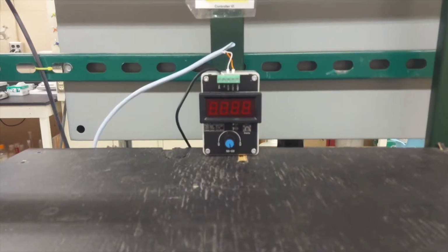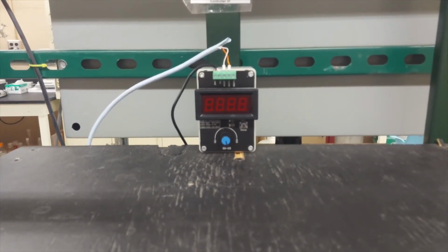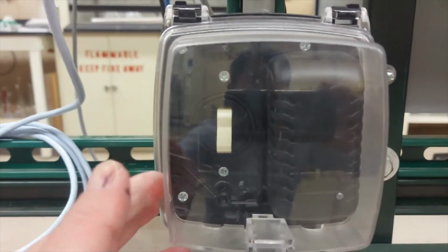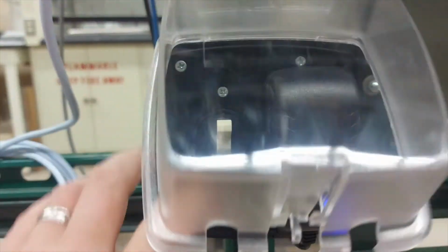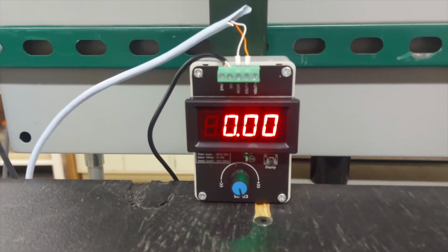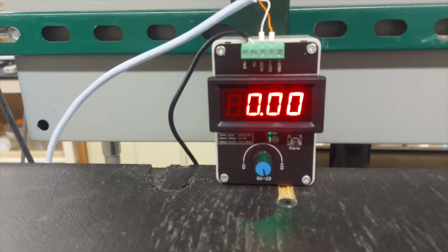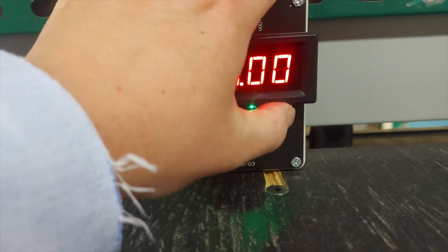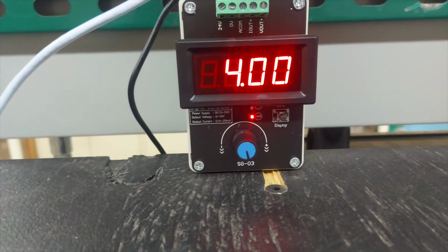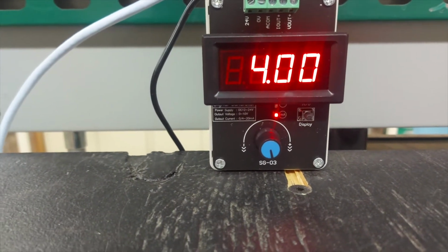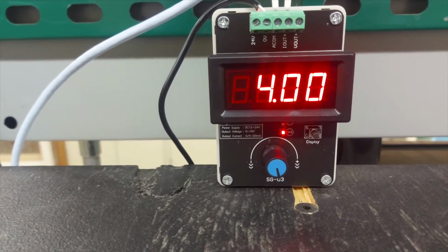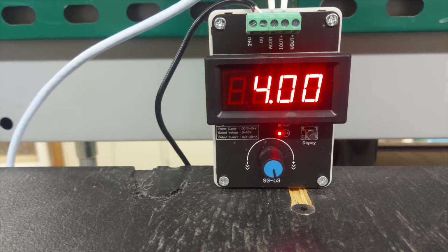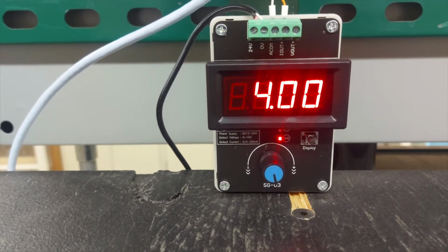In order to operate the pump valve, we will be using this control box. To begin, turn on the switch so that the valve actuator's blue LED light turns on. This also results in the control box's display turning on. If the green LED light is on, press the display button to switch it to red so that the control box is in milliamps. The lowest value for the control box on this setting is 4 milliamps, which corresponds with the valve being completely closed.